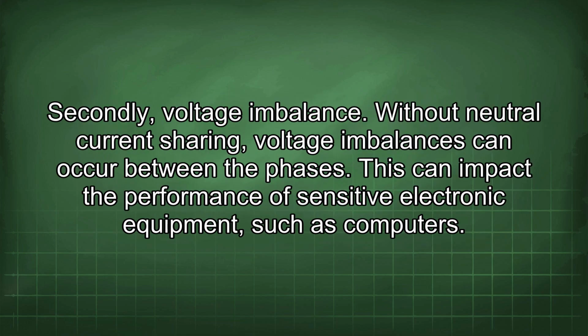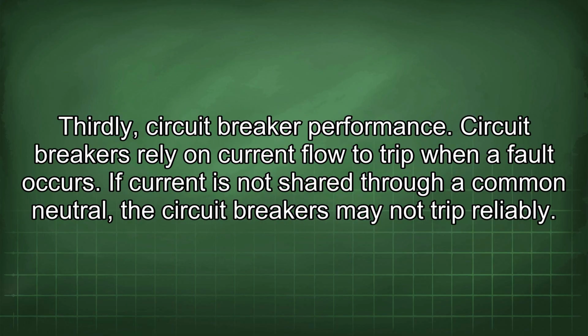Secondly, voltage imbalance. Without neutral current sharing, voltage imbalances can occur between the phases. This can impact the performance of sensitive electronic equipment such as computers. Thirdly, circuit breaker performance. Circuit breakers rely on current flow to trip when a fault occurs. If current is not shared through a common neutral, the circuit breakers may not trip reliably.